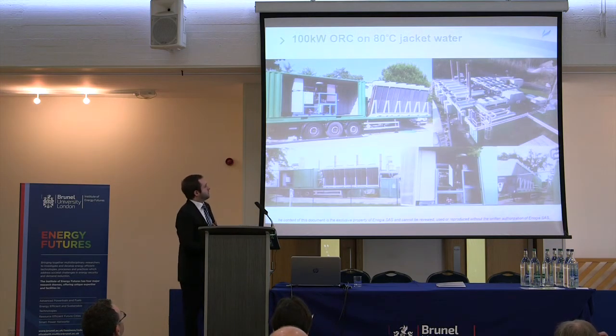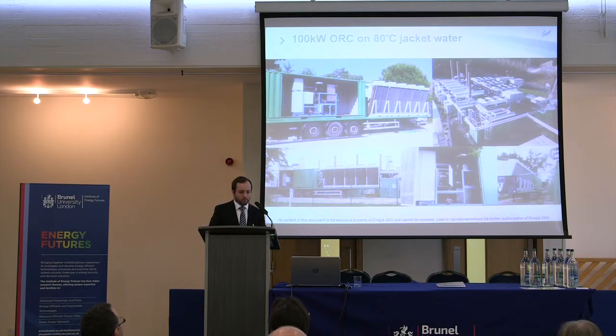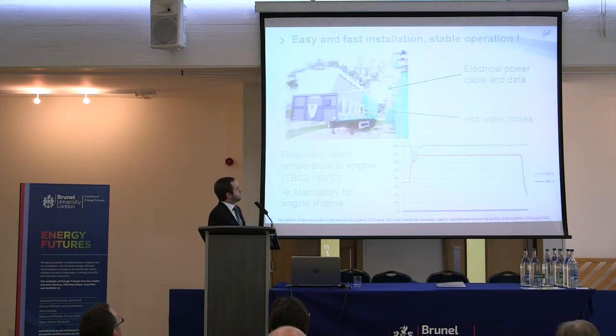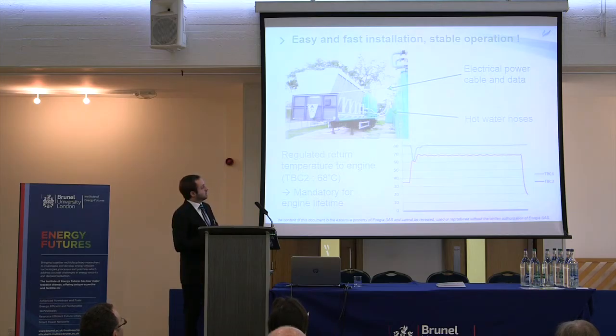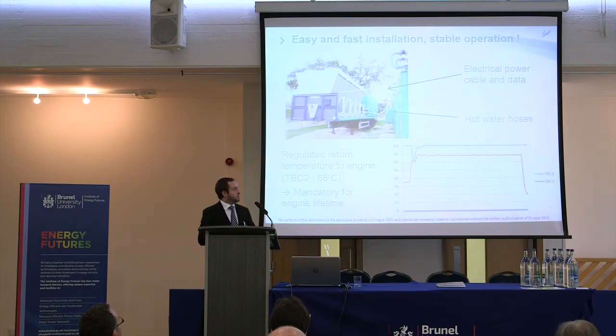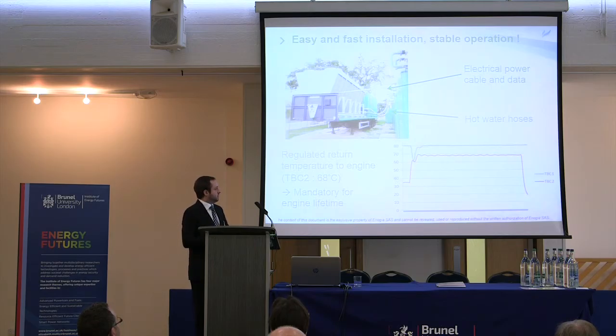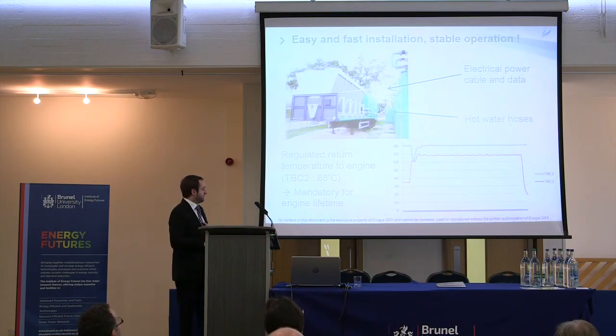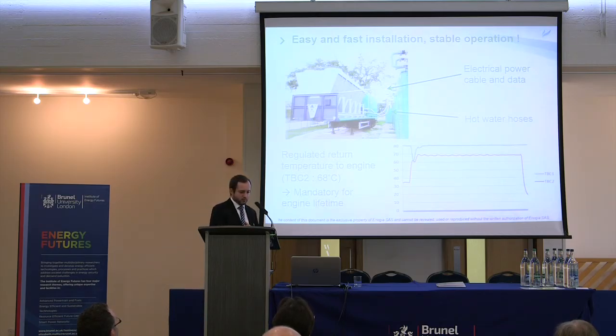We installed this unit on an anaerobic digestion power plant in France, running on low temperature engine heat. You can see it's very simple to install, with 2 water hoses and 1 electrical cable. A very nice feature of this unit and the evaporating scheme in the ORC is that the return temperature to the engine is very stable. The goal is to reach 68 degrees, and on this graph you can see the oscillation is no more than 1 degree. This is mandatory for engine lifetime in anaerobic digestion plants.